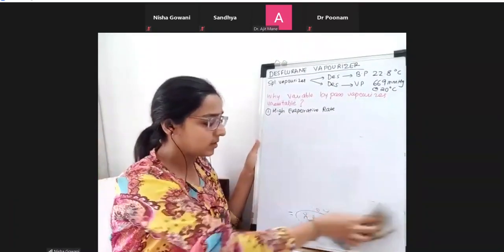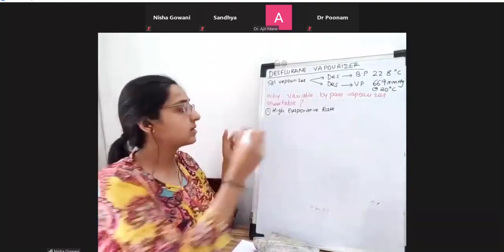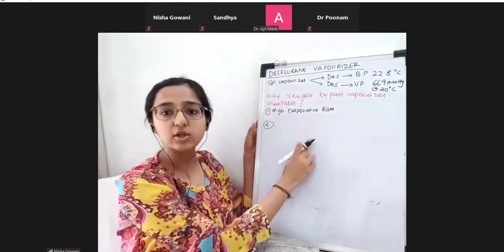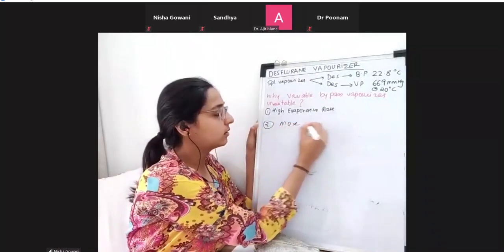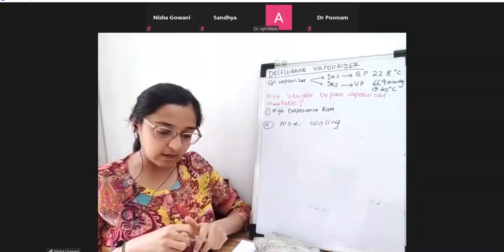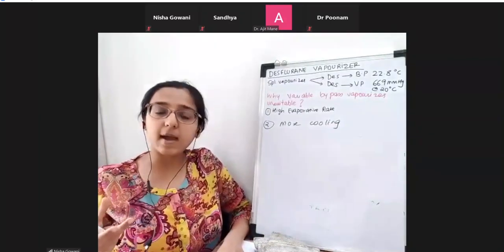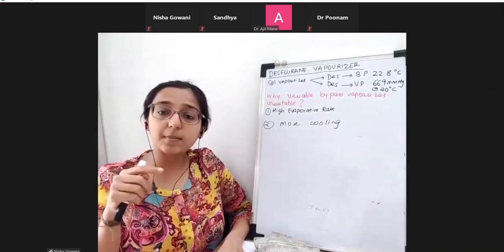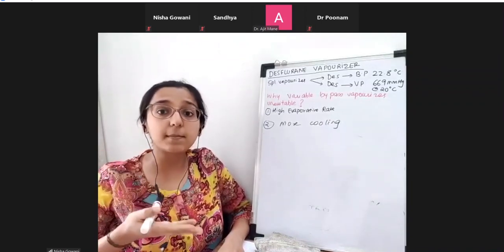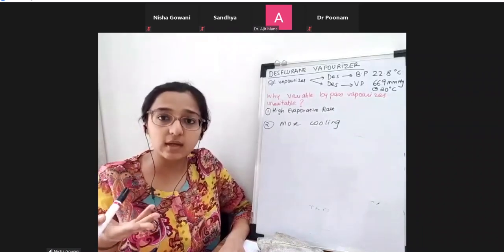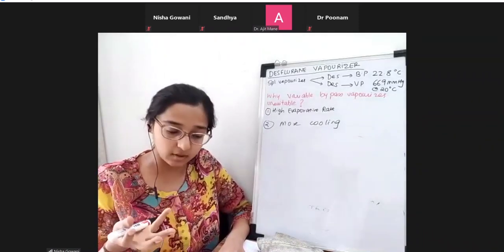Okay. Now the second reason is what? There is a high evaporative rate that we know. More evaporation means what? There will be more cooling, right? So this is a second problem which occurs with desflurane. If you use the variable bypass vaporizer which I showed you right now, and the saturated vapor concentration is 88%, that much volume of desflurane is getting converted to vapor. That means that much cooling will occur in that vaporizing chamber, right?